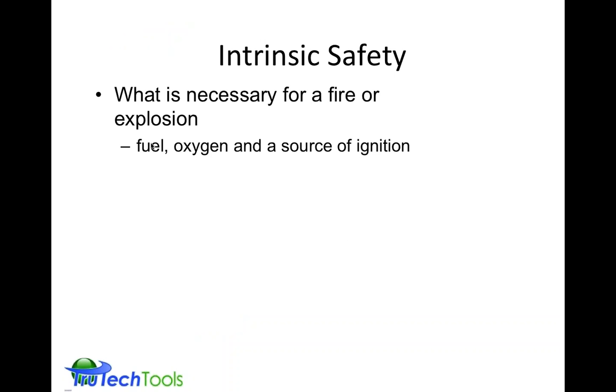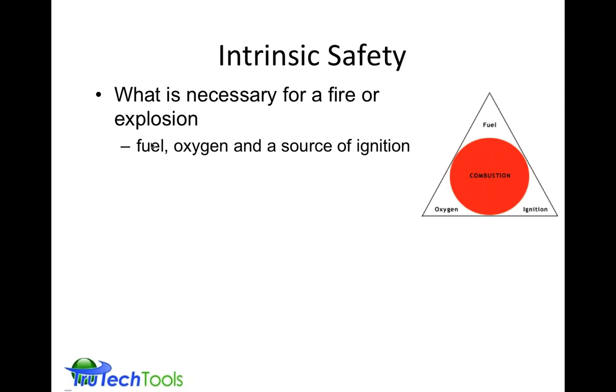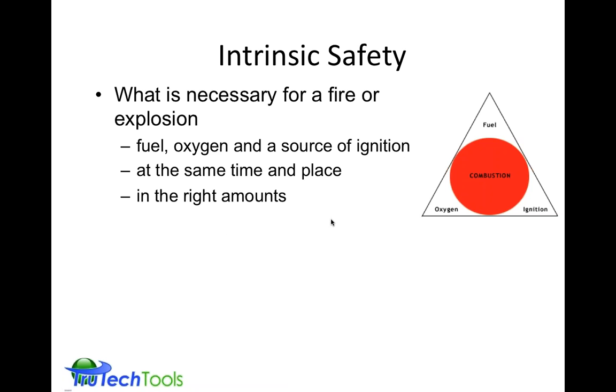So what's necessary for a fire or explosion when we're talking about intrinsic safety? It really goes back to the combustion triangle. There needs to be fuel, sufficient oxygen, and a source of ignition for combustion to happen. It has to be at the same time and the same place and in the correct quantities. So the right amount of fuel to oxygen and the right amount of energy in the ignition. Now usually the device, the intrinsically safe device, is what controls this aspect of ignition, the thermal or electrical energy present that could cause this ignition to happen.